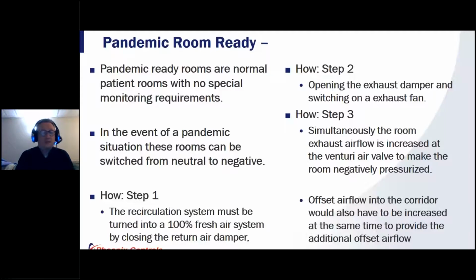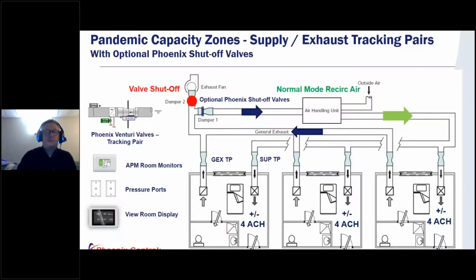So again, 3 easy steps. The recirculation system is turned to a 100% fresh air system, closing the damper, right? Then we open the exhaust damper, switching on the exhaust fan, and then we increase the exhaust airflow within those spaces, and then we bring in some makeup air into the adjacent corridor, right, to compensate for that offset air. So pretty simple, right? All done within a control sequence.